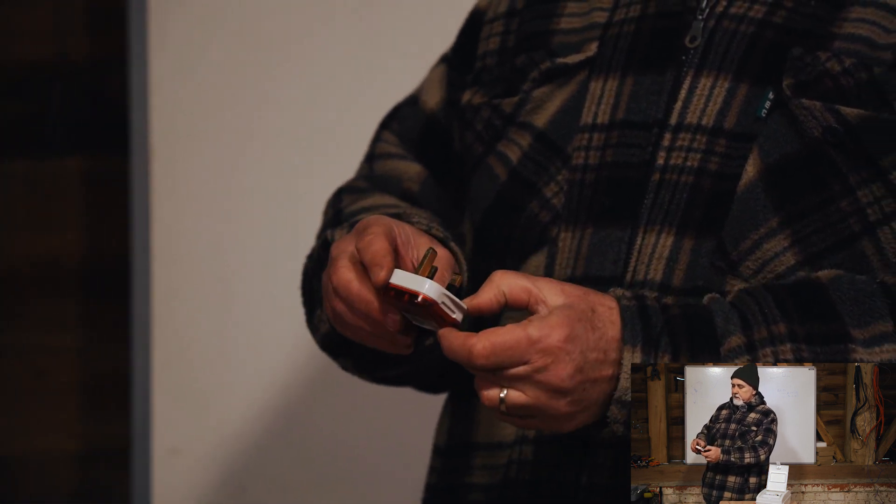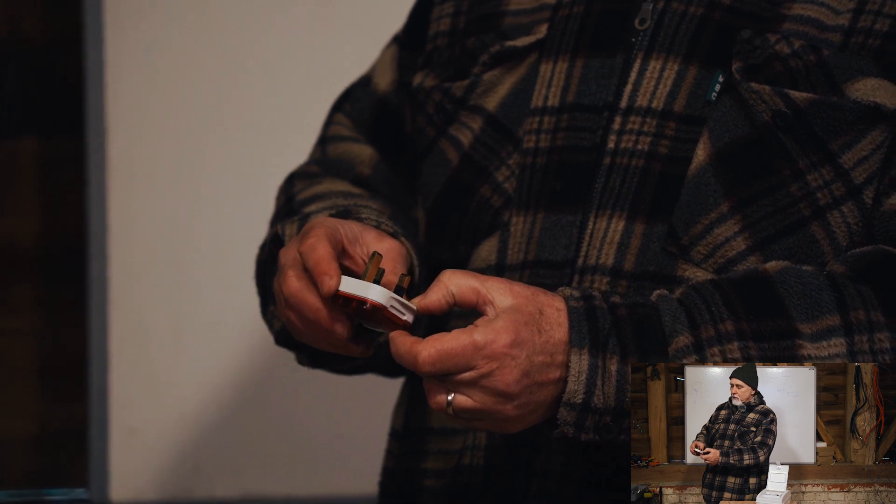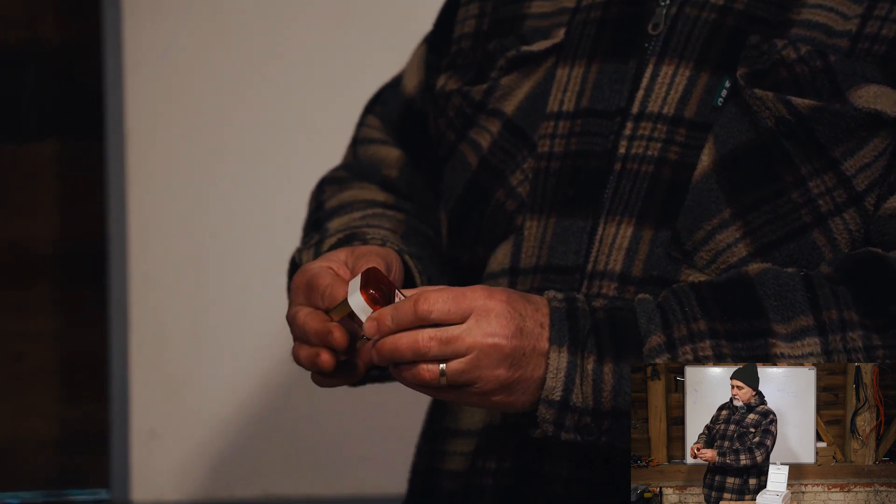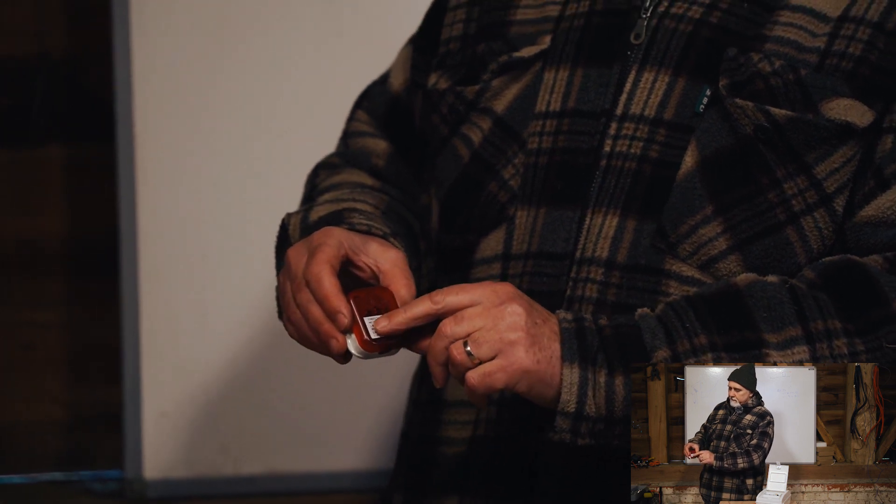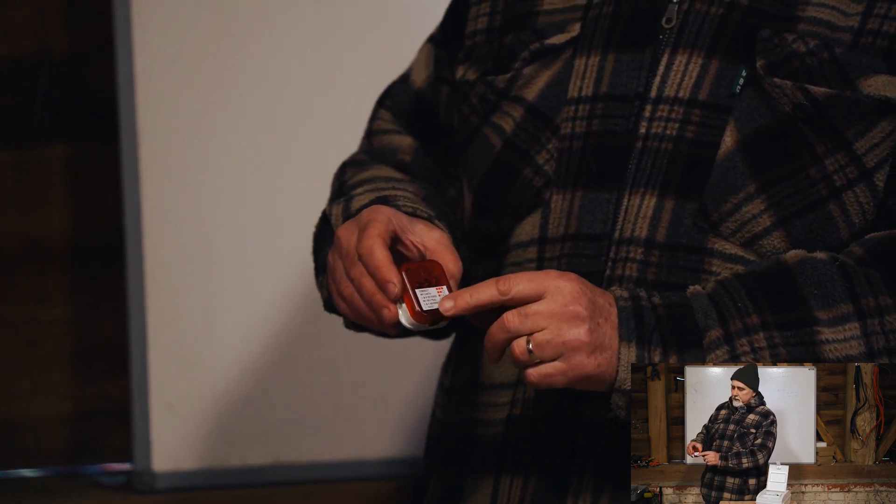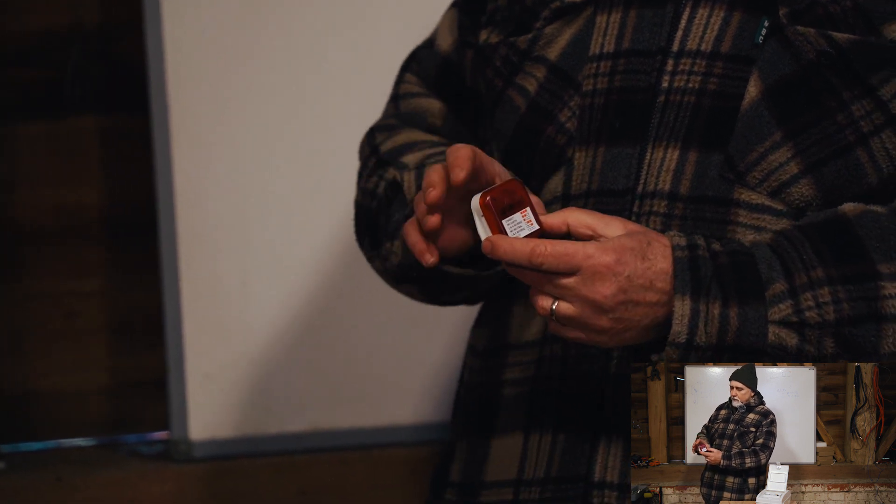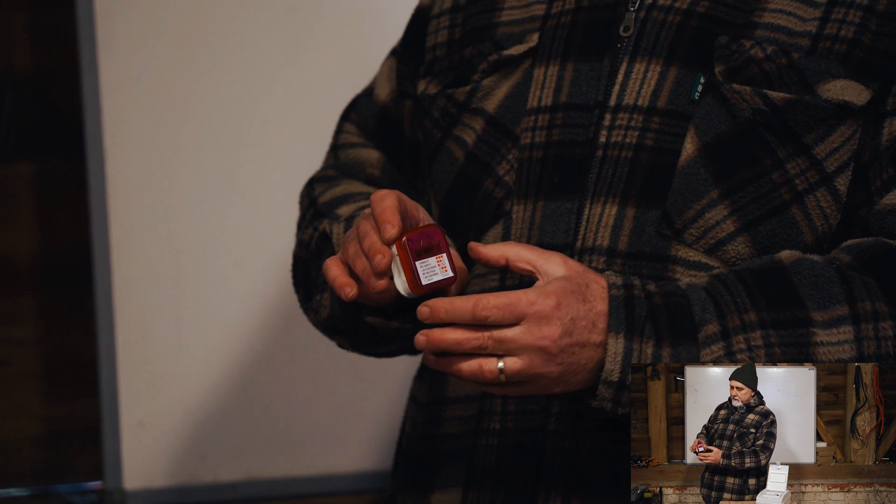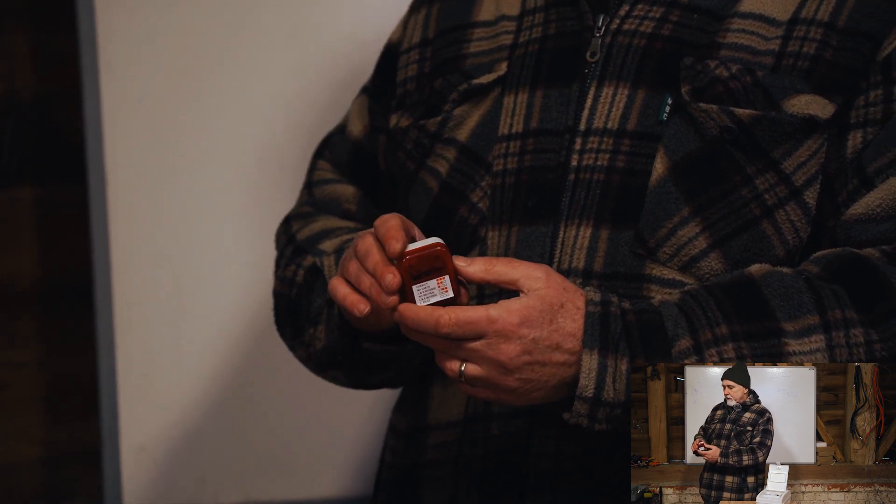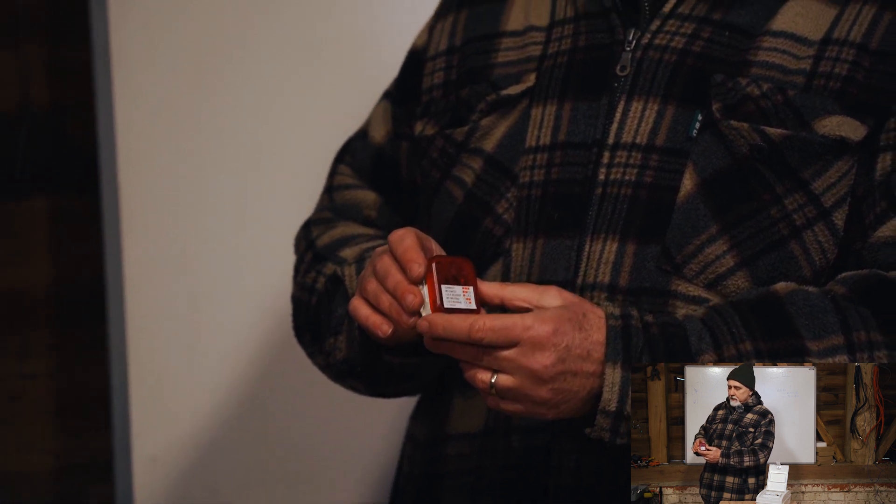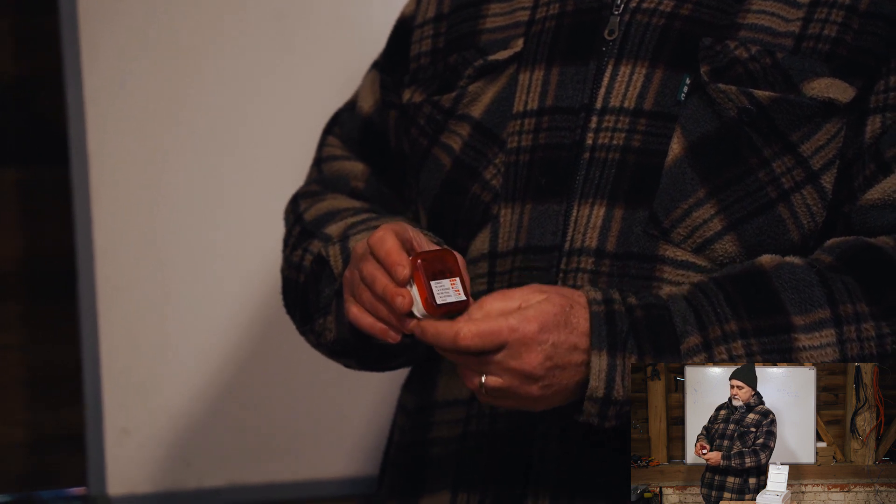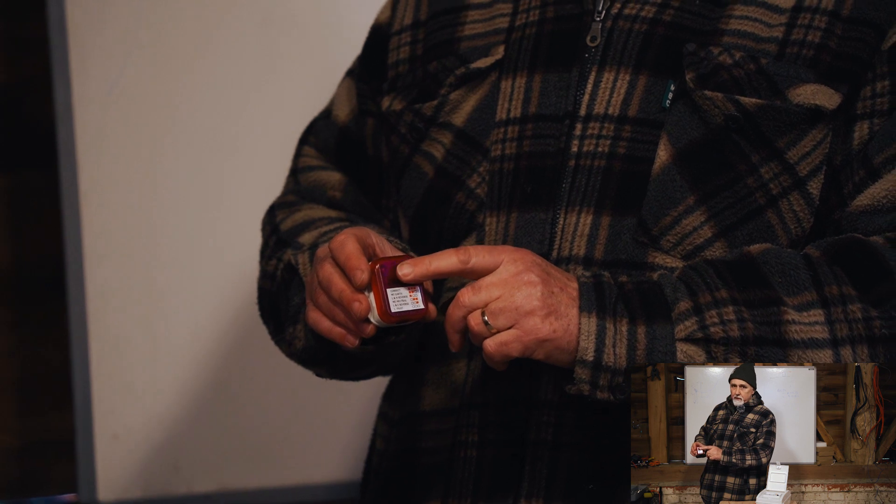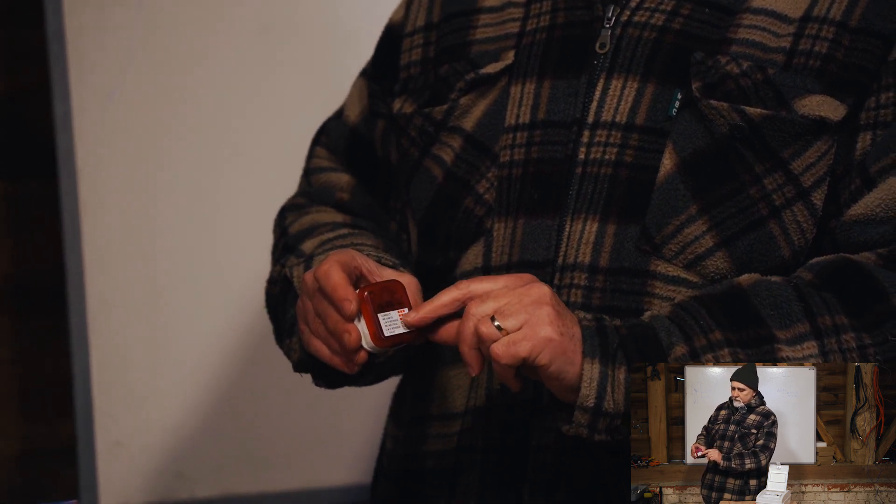These are inexpensive devices. And I don't know exactly what they're called, but we'll find the link and stick it at the bottom of this so that you can see where you can buy such a device. They're fairly inexpensive and they are quite reliable. I find that they do warm up. And in some cases, you see that they have a continuous sort of buzz when they are operating. So perhaps don't leave it plugged in permanently. Plug it in just when you need to actually check the wiring that's coming in. But they are really handy because at a glance, you plug it in and it tells you a lot of really important information. And what you want is the top option where it shows that everything is correct with all three LEDs lighting up.